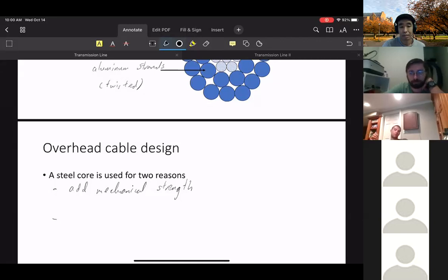The power is consumed. Right, it consumes power, it's a resistor, power goes to heat. But if you look at a line, once it starts to heat up, what do you see? Mechanically, what happens to a line once it starts to heat up? It'll sag. Why does it sag? Because the wire is longer. Thermal expansion. If it heats up, the thing gets longer. It has to go somewhere, so the only place to go is to sag.